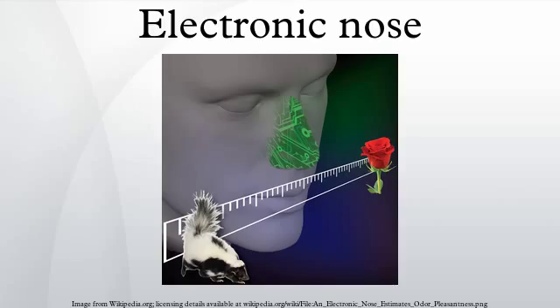More recently they can also address public concerns in terms of olfactive nuisance monitoring with networks of on-field devices. Since emission rates on a site can be extremely variable for some sources, the electronic nose can provide a tool to track fluctuations and trends and assess the situation in real time. It improves understanding of critical sources, leading to proactive odor management.